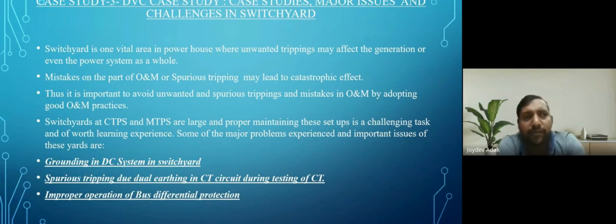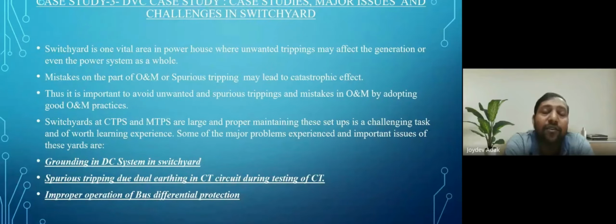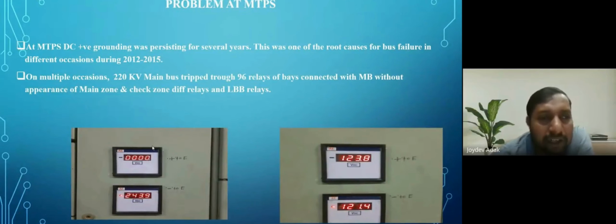But in the case of Mejia and Chandrapura thermal power stations, these two have the biggest switchyards in the eastern side. In such a big switchyard, DC flows from one end to another, and there are very long DC circuits. Due to these long circuits, from 2012 to 2015 there was grounding at the positive side. This was the voltage profile, the initial condition: 0 volt at the positive end, with positive to ground and negative to ground readings. But ideally it should be around 50-50.